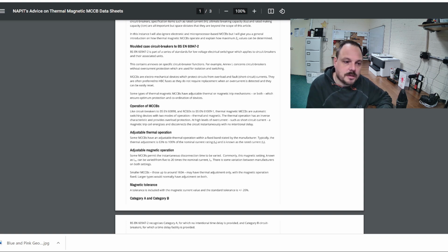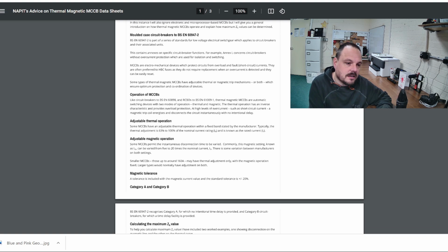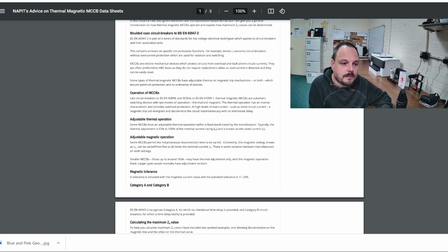There's some variation between manufacturers on both settings, and that's important to note. It's different in the way that they're labelled on the actual dials. Some of them use a percentage, some of them use the actual values, and again you can set them based on what you want the instantaneous tripping characteristics to be. Smaller MCCBs, those up to around 160 amp, may have thermal adjustment only with the magnetic operation fixed, and larger types would normally have adjustment on both.